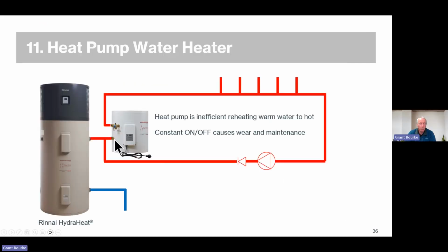Heat pump water heater, different story. Heat pumps are inefficient at heating warm water to hot, and turning it on and off, just keeping the ring main hot, will wear the heat pump out really quickly. So what we do is we have a ring main reheating cylinder. We get a small electric cylinder. We run the heat pump feed into it. We run that around the house, and we run the return back. And the element in this cylinder is making up the heat loss of the ring main. So it reduces the wear on our heat pump, and it makes it work a lot more efficiently.